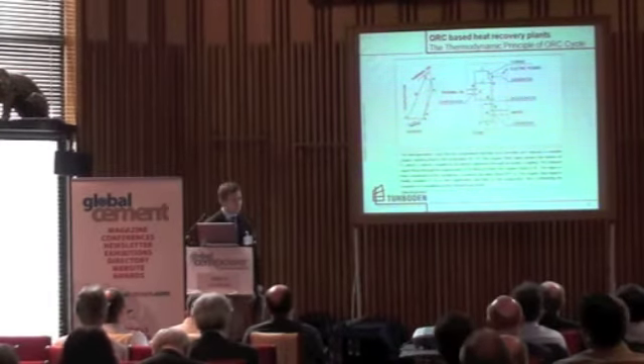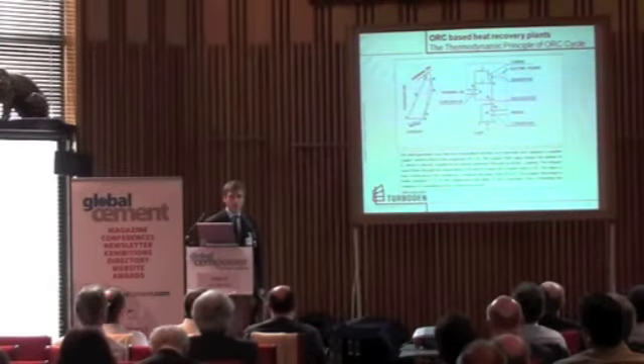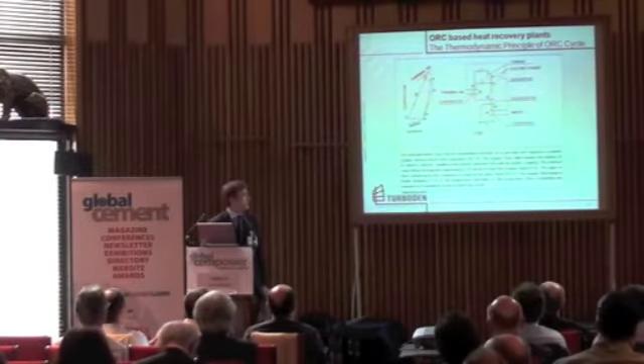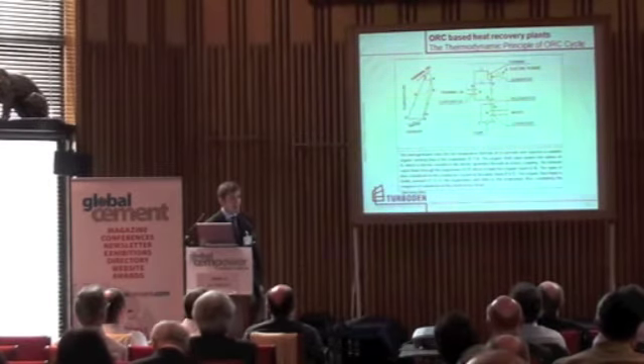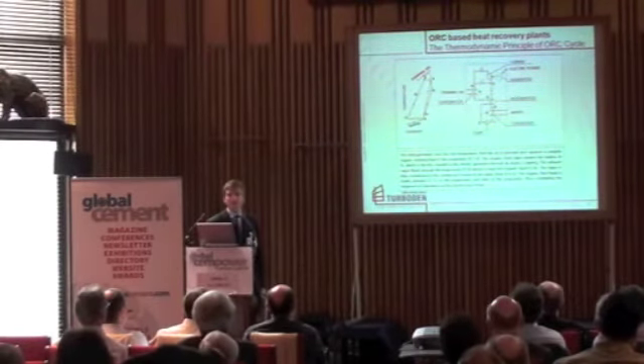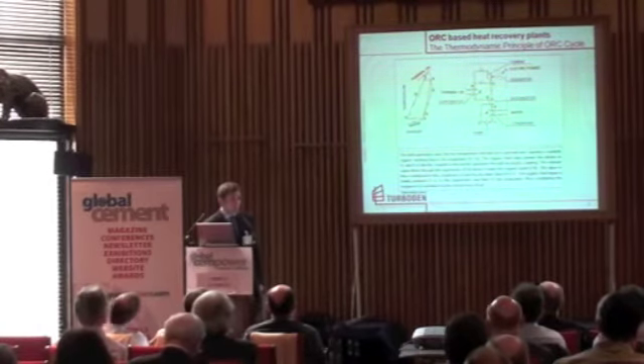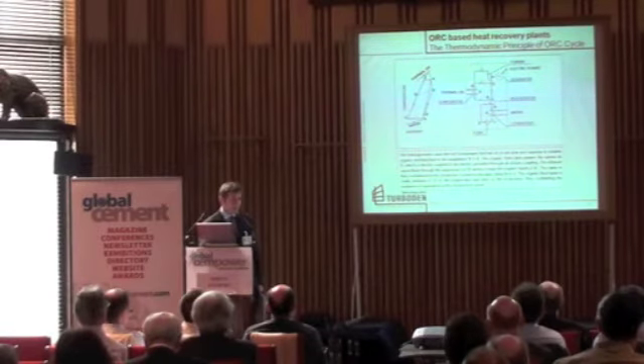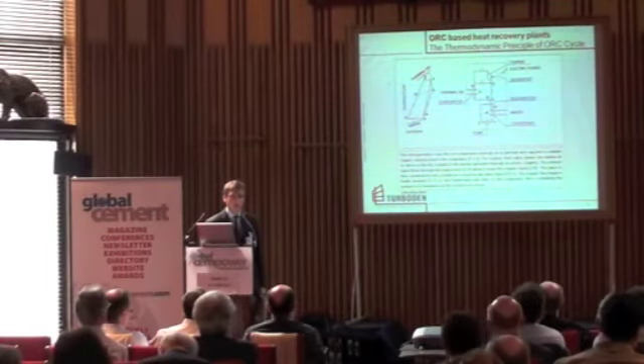So thanks to the typical shape of the equilibrium curve, we do not have the need for superheating, so it makes the system more easily managed. The enthalpy drop across the turbine is much lower than in the traditional water steam or ammonia cycle. So we will see later how these two aspects affect the operational condition of the organic system.